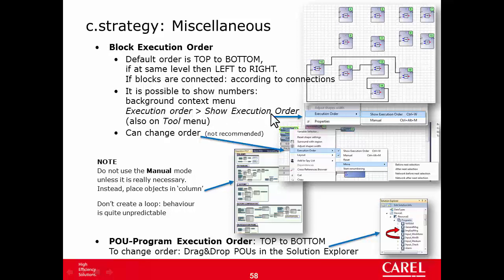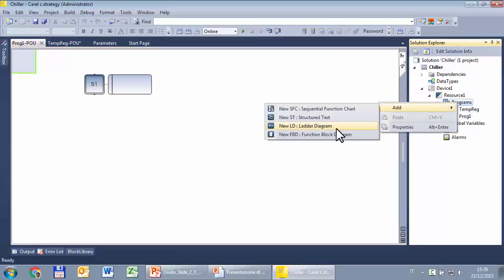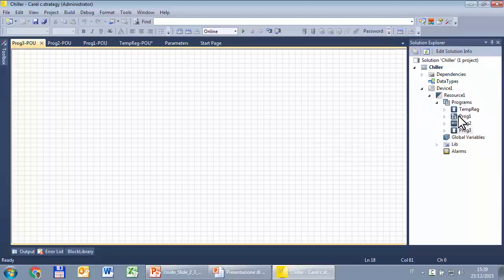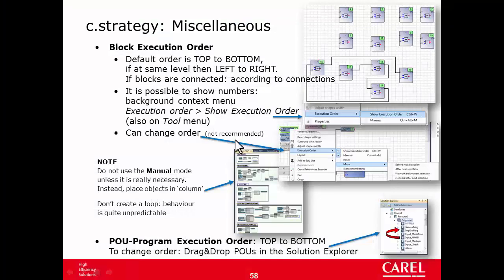What I told you regards the blocks of a given POU, given page, but what about the POUs in a given application? The POUs are executed from top to bottom, like in OneTool, according to the sequence here in the solution explorer. For example, if I create a new POU, the execution order will be from top to bottom. You can easily change the sequence with a simple drag and drop. Drag and drop at the end. Well, this is all regarding the block execution order.